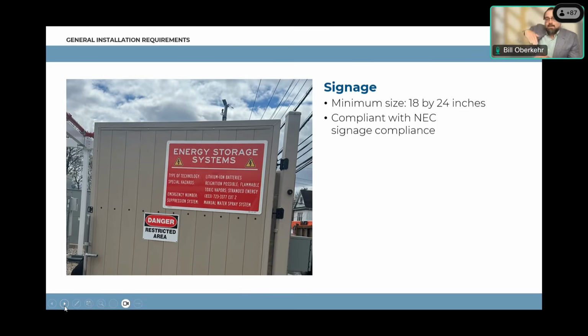Sometimes that pop of the vent can pop off of the container. So part of that site map and hazard warnings on the signage needs to identify if that happens -- if there are deflagration panels, the site map and hazard warnings need to show where they are. They also need to identify where that vent might land if it were to blow off the system. These are the types of things we're looking for in the code requirements around hazard warnings.